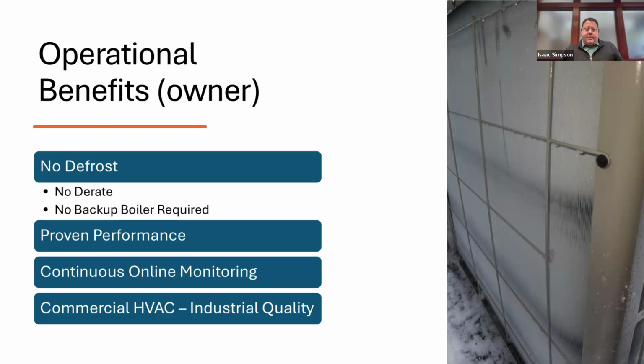And there's a couple things that come from that. One, you have an energy penalty. You're stopping the heating going into the building while you're running in cooling, and there's an energy cost to de-icing or defrosting the coil. You have to make that up somehow. You have to either have another source of heat, another heat pump, a larger system, or some backup heat, which often has been done with resistance heat, which has a very low COP of 1.0. So you're either using some resistive heat, some backup boiler, or you're paying for a lot more heat pump.